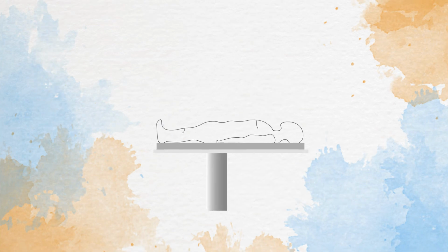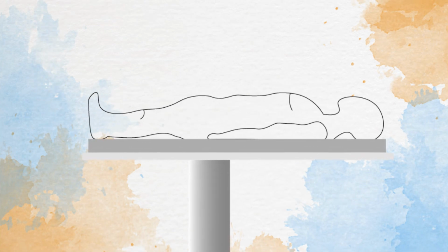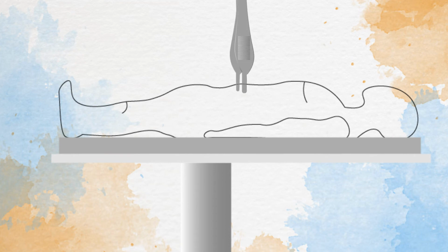This difference between the bipolar and the monopolar is how and where that return electrode is used. Bipolar generally uses a forceps-like tool, wherein the active electrode and the return electrode are at the same surgical site at the tip of the forceps. The forceps can grasp any tissue, and since it's between those electrodes, only that tissue is affected.